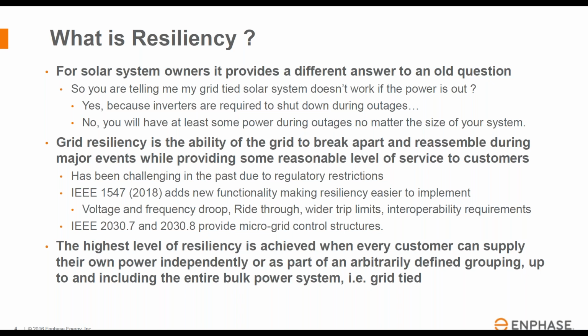We just published, actually last week, a new version of IEEE 1547, which is the new interconnection standard for the United States. It adds some new functionality, which actually makes it easier or even possible to implement functionality that would provide resiliency. Principally, that's in the form of voltage and frequency ride-through, tripping, and most importantly, I think, some standardized interoperability requirements so that these systems can communicate to the utility or to whoever is operating the microgrid during one of these events.